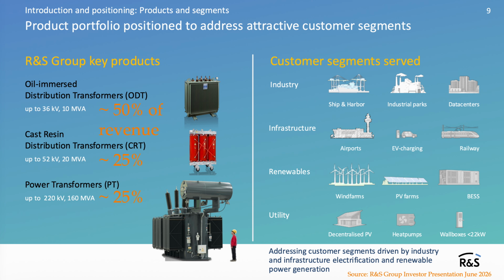Cast resin transformers remove the flammable oil and use epoxy resin for insulation and fans for cooling. They are more expensive and are used in environments where fire is not a risk that can be tolerated, like inside buildings, hospitals, data centers, ships, tunnels, offshore platforms, and similar places.